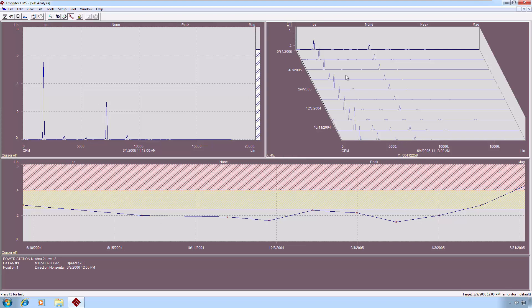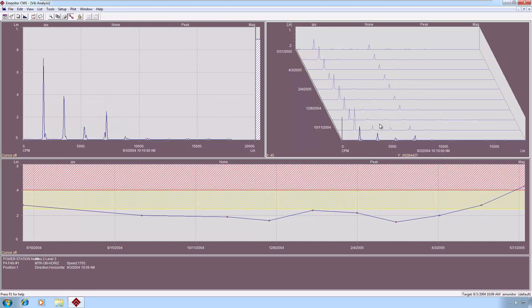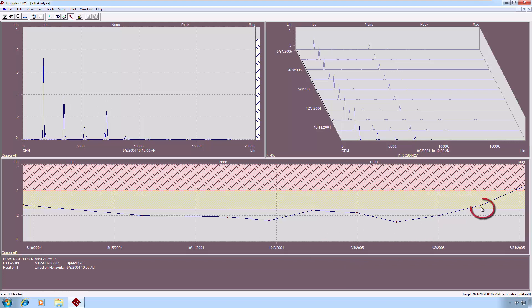If I'm working from the waterfall, I can position the cursor on the waterfall I'm interested in, and it will activate the current spectrum with that as well. Now, it might be that I want to click on the first data point that has gone into alarm, because in this particular data point, I'm looking at the overall, and the overall tells me something has changed, but it does not tell me what's driving that change.